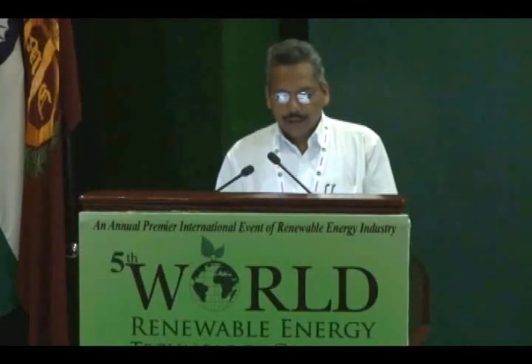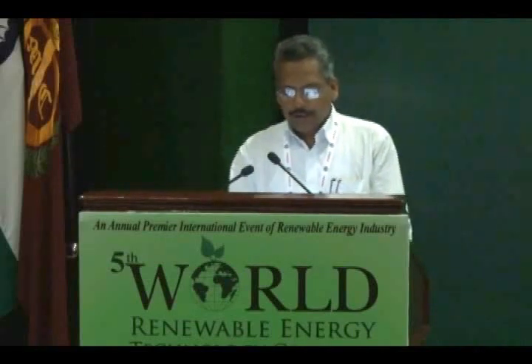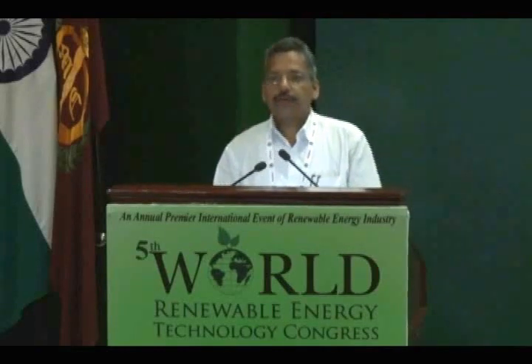This is a typical grid monitoring station where instruments are installed along with a data logger — this is how we are doing it conventionally. Now we are introducing remote sensing. For example, for a 5 MW wind turbine, the wind speed at 100 meter height measured by a single cup anemometer is not representative. Using remote sensing techniques — basically SODAR and LIDAR — we can probe heights up to 1 or 2 kilometers.